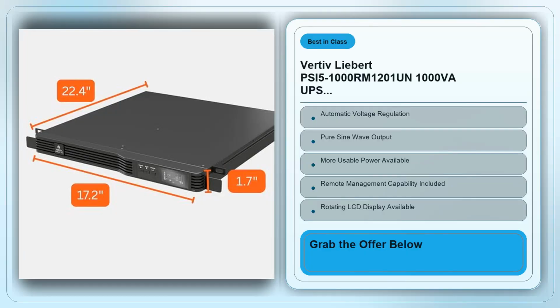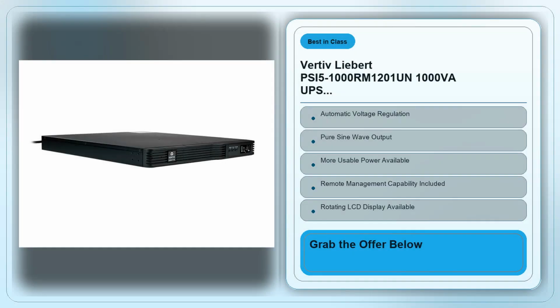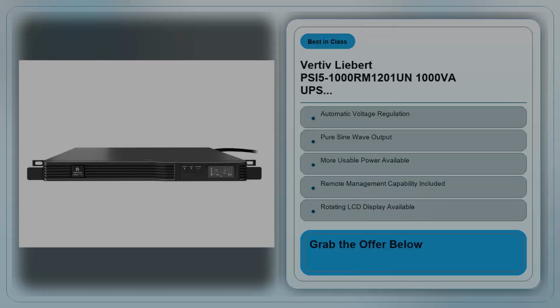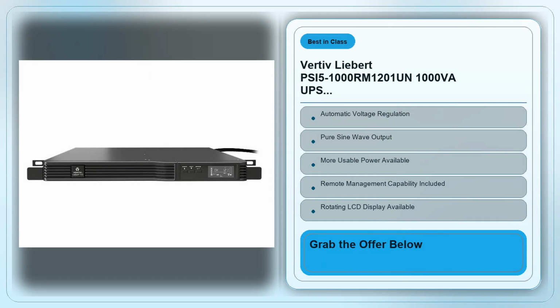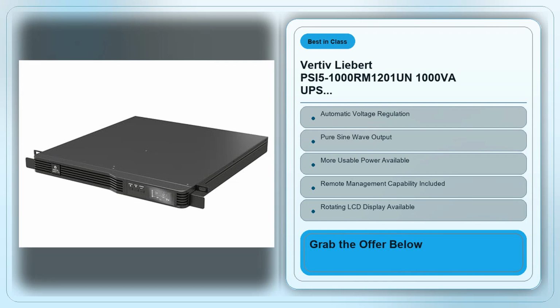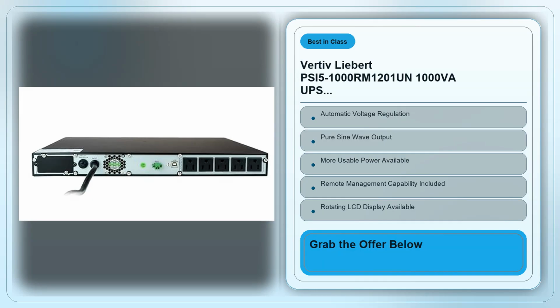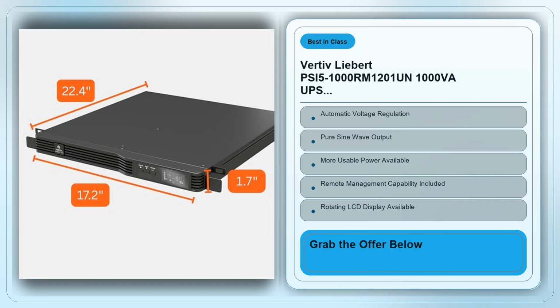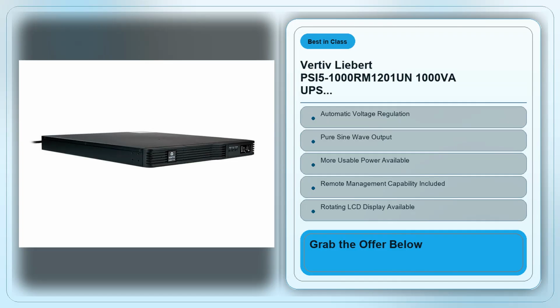Of course, there are practical weaknesses you need to weigh. The 1000VA rating translates to roughly 600 W of usable power. That means you have to be careful about the total load you place on the unit. A typical 4-core workstation with a mid-range GPU can pull around 350 W at idle, but spike up to 500 W under load. Add a NAS, a PoE switch, and a small server, and you're flirting with the limit. If you exceed the capacity, the unit will either overload or initiate a shutdown, which defeats the purpose of backup. So it's essential to calculate your peak load before you buy, and perhaps leave a 20–30% headroom.